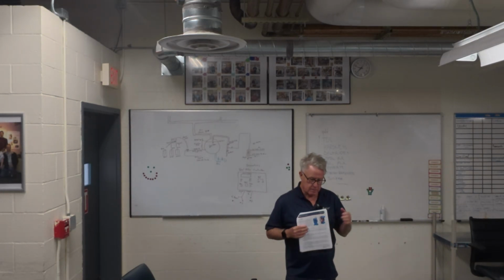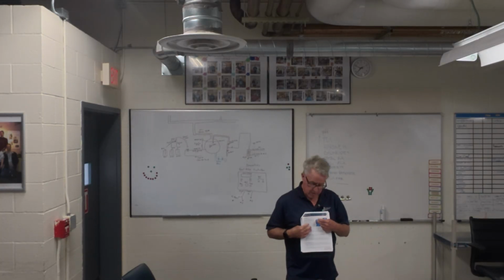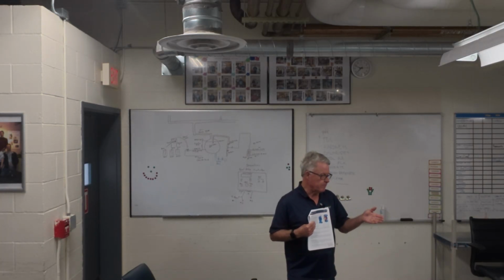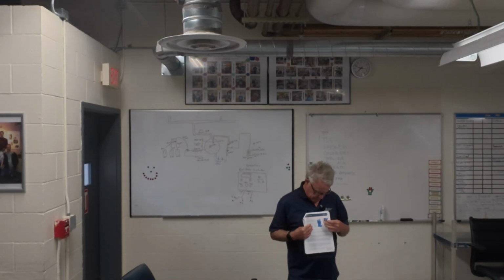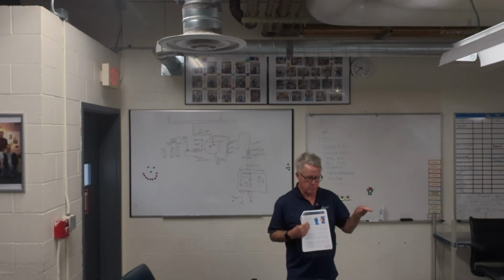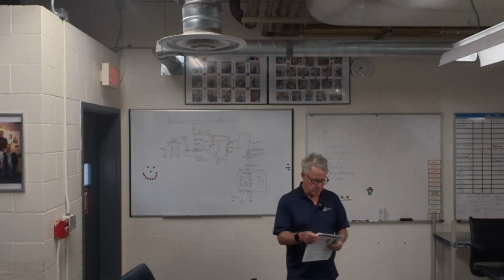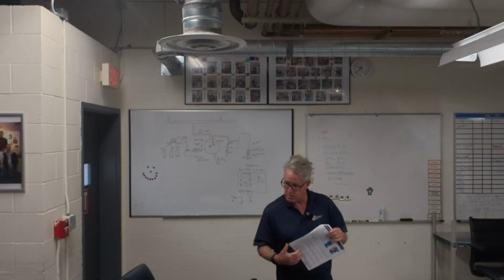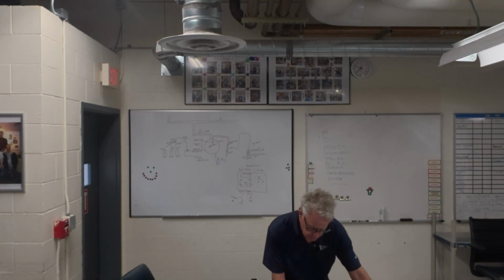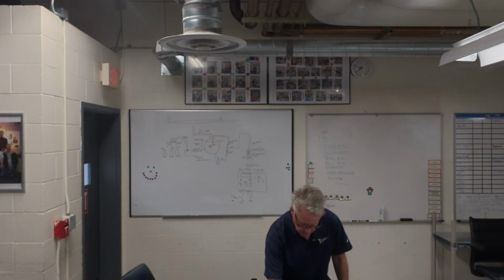There's a couple ways to manage this. We can manage it through the pulse rate on the pumps, or we can manage it through accumulation of the water. So in locations where we have this, you can really start to fine tune the water chemistry for it. Again, it's a little new here, but we're heading toward that type of situation where we can super fine tune this. Injection quills, that's separate because we're injecting directly into the boiler, and I covered the symmetric controller.